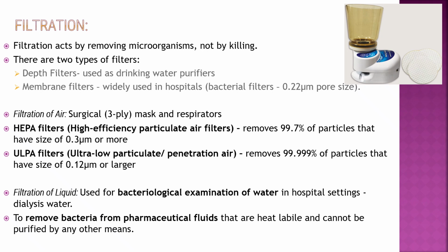HEPA filters, high efficiency particulate air filters, remove 99.97% of particles that have a size of 0.3 micrometer or more. ULPA filters, ultra low penetration air filters, remove 99.999% of particles that have a size of 0.12 micrometer or larger. Filtration of liquid is used for bacteriological examination of water in hospital settings, dialysis water, and to remove bacteria from pharmaceutical fluids that are heat labile and cannot be purified by any other means.